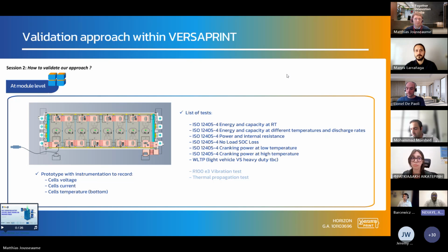We also test the SOC loss to check the auto-discharge of the system, because there is a direct relation between the SOC loss and the SOH, the state of health. During the test we check the discharge of the component after 1 day, after 1 week, and after 1 month, without plugging in anything.